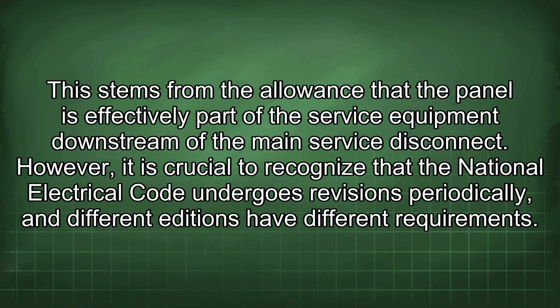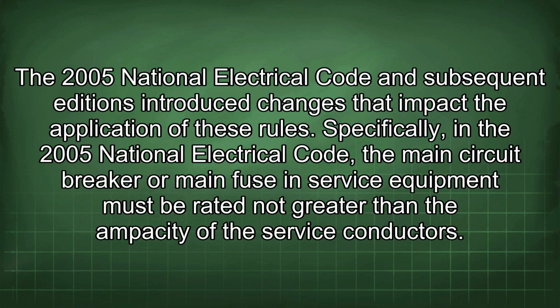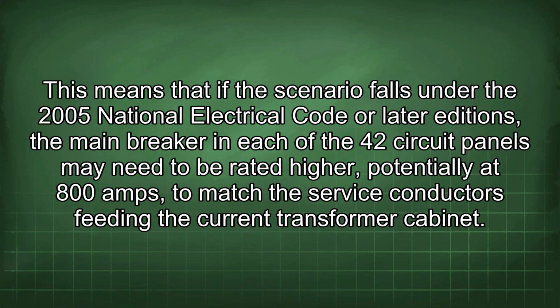This stems from the allowance that the panel is effectively part of the service equipment downstream of the main service disconnect. However, it is crucial to recognize that the National Electrical Code undergoes revisions periodically and different editions have different requirements. The 2005 National Electrical Code and subsequent editions introduce changes that impact the application of these rules. Specifically, in the 2005 National Electrical Code, the main circuit breaker or main fuse in service equipment must be rated not greater than the ampacity of the service conductors. This means that if the scenario falls under the 2005 National Electrical Code or later editions, the main breaker in each of the 42 circuit panels may need to be rated higher, potentially at 800 amps, to match the service conductors feeding the current transformer cabinet.